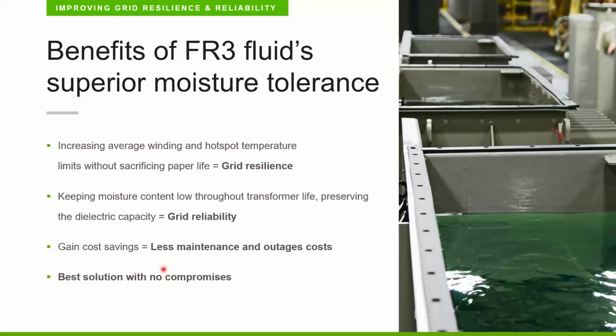Oh, yeah, sure. The retrofilling of transformers already in use is something that is becoming more important nowadays for several reasons. As you said, one of those reasons is to extend the life of the asset. If the transformer is in the middle of its lifetime, by replacing the mineral oil with FR3, we can take advantage of this continuous drying, so we will extend the life of the transformer. It's also true that we have the advantage of overload. The transformer can be overloaded by this.